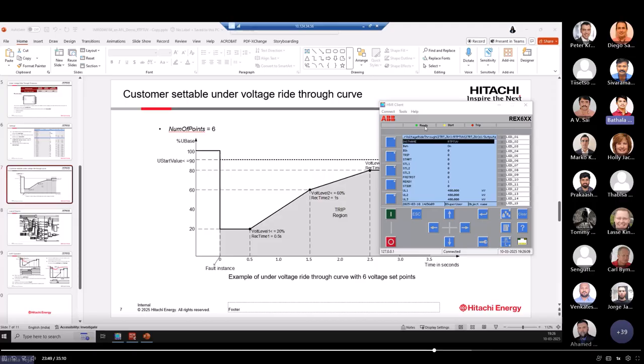One more example I want to show here is how the fast reset works. So I will change the first setting. Fast reset is off right now. I'm turning it on. I'll put T fast reset as 2 seconds. Within 2 seconds, if the voltage has recovered, then start will reset immediately. It won't even wait for the curve to end. So fast reset 90%, that's fine.